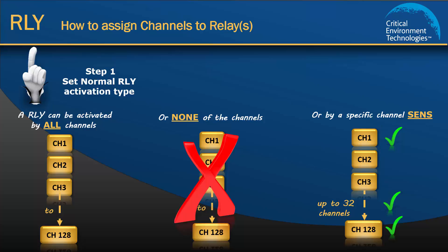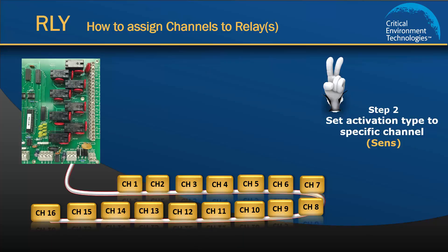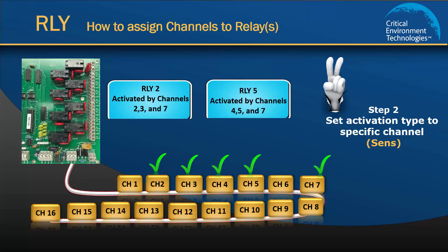In this exercise, we want to assign specific channels to Relay 2 and Relay 5. To do this, we need to set the activation type for Relay 2 and Relay 5 to Sens, and then assign channels 2, 3, and 7 to Relay 2, and assign channels 4, 5, and 7 to Relay 5.